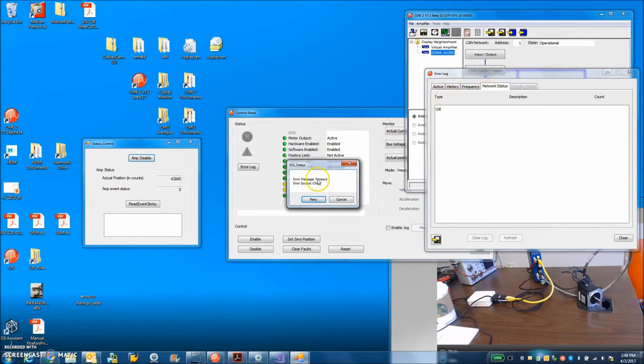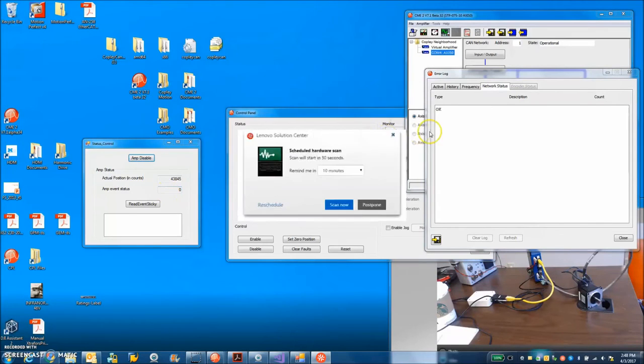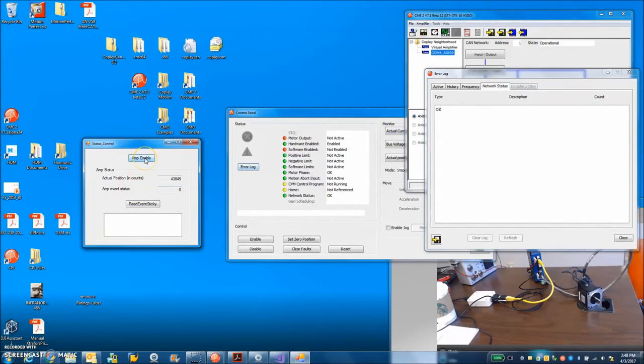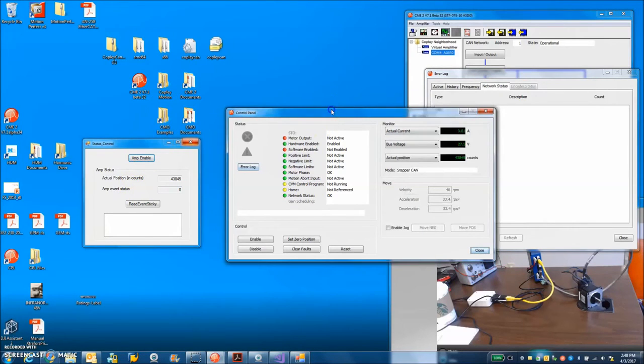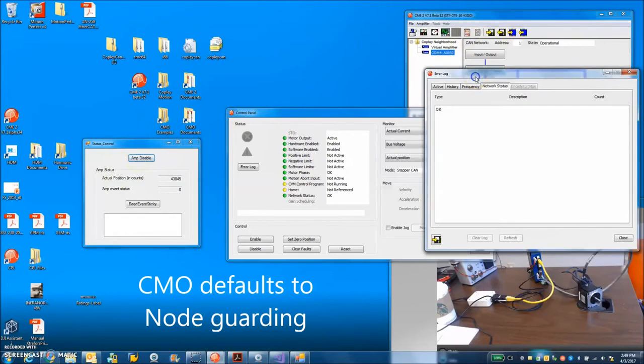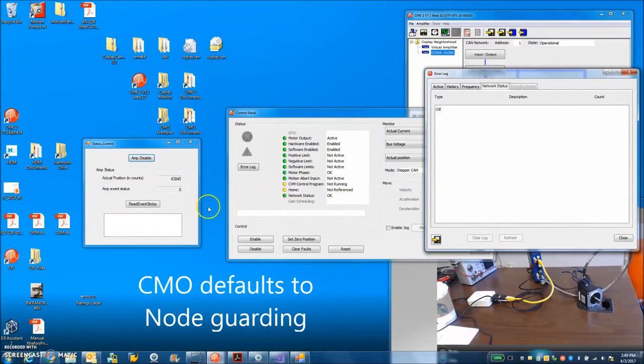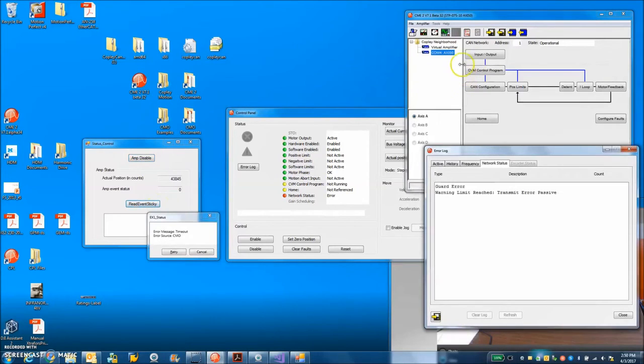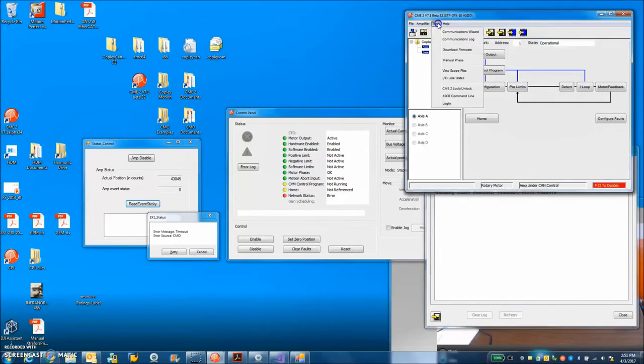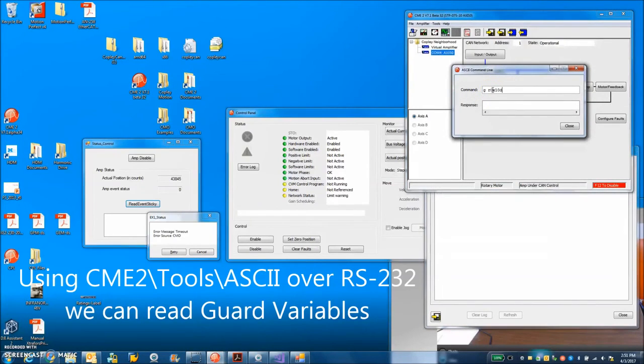Well, the master is still there. That's good. Let's retry this. So disable, enable, not bad. So yeah, if you're trying to do something when the drive's disabled, you can see the node guarding is taking effect. I'm going to check out the guard parameters here.